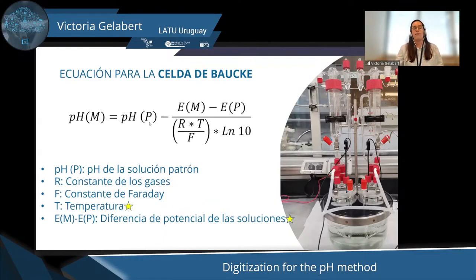So we're going to have the assigned value for the primary reference material. This cell depends strictly on a previous pH value. Here we're always going to be using a primary reference material where the value is assigned by NIST, because we always work with NIST. So this is a fixed entry for the system. And here we're going to have the gas constant and the Faraday constant. And up here, we also have two other entries, which are going to be the potential difference generated between both compartments.